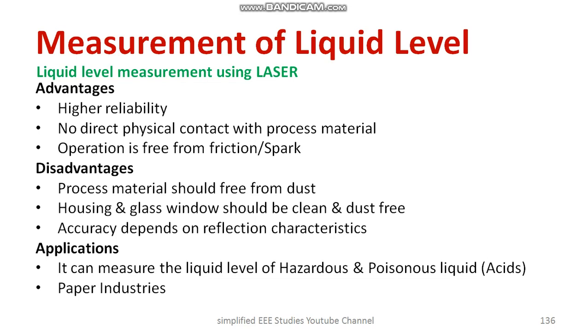What are the major drawbacks? The process material should be free from dust, moisture content, etc. Also, the housing and glass window should be kept clean and dust-free; otherwise your readings become wrong, because the laser has to pass through the glass. Accuracy depends on the reflection characteristics, which depends on the type of liquid, the glass material, refractive index — everything matters a lot.